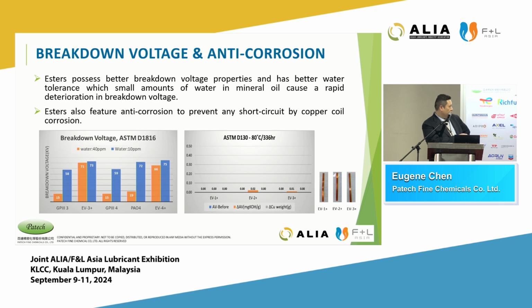You can see that even when moisture is introduced, ester tends to be very stable in terms of breakdown voltage, whereas the other hydrocarbon-based material shows a significant drop in breakdown voltage once you increase the moisture content. One critical thing to consider is that when a system comes into contact with an electric motor, you want to ensure it has good breakdown voltage or electrical resistance performance.